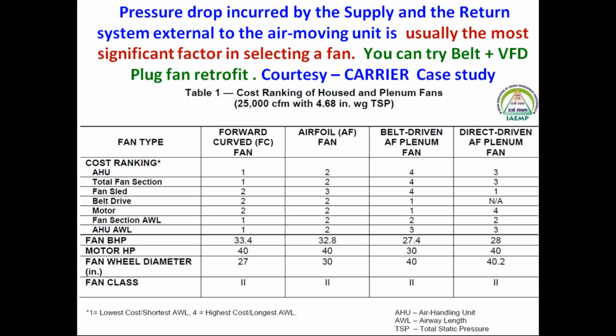So this is applied to the HVAC segment, where when you go for an energy audit, we can suggest that instead of a forward curved fan, you can go for a backward curved centrifugal fan, or the best is the plug fan or the plenum fan, which is used especially in the HVAC segments, especially in the cleaner segments, like environment. It gives energy savings of almost 20%. Next, please.